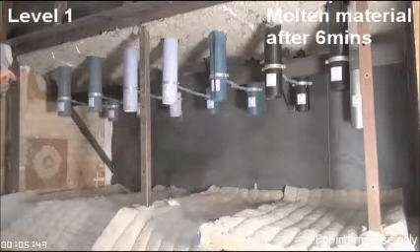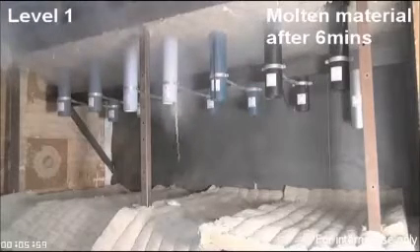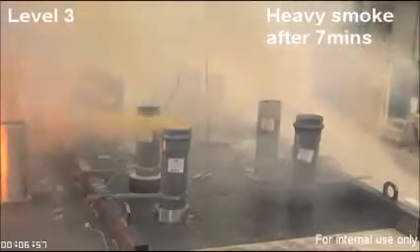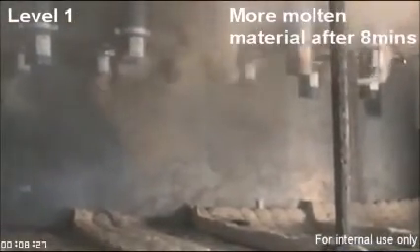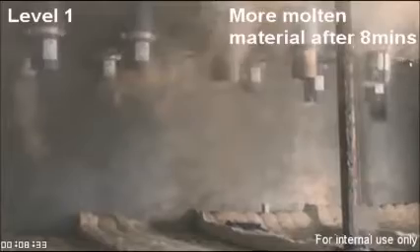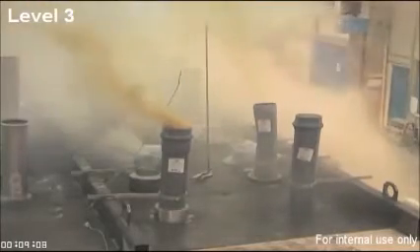Just after five minutes and forty-eight seconds, the PP pipe creates melting droplets falling to the lower deck. After eight and a half minutes, smoke is also created in the lower deck along with melting droplets of plastic. The pipes going through the upper deck have started to melt and deform, and the development of toxic smoke is now very significant.